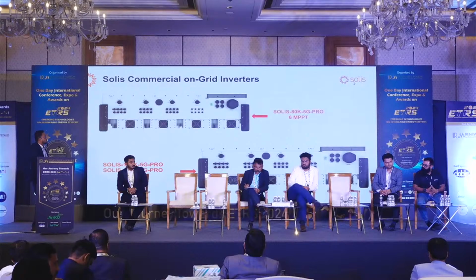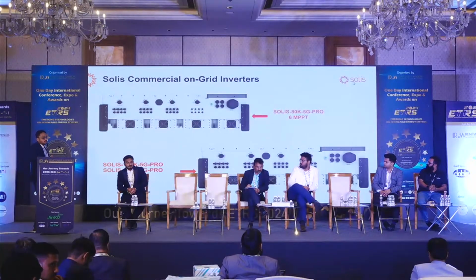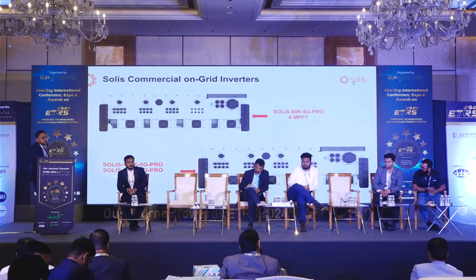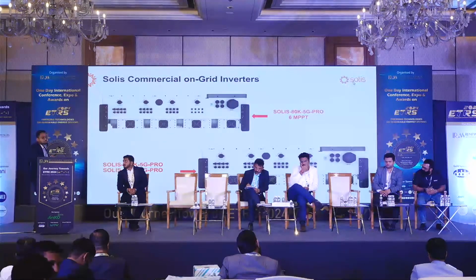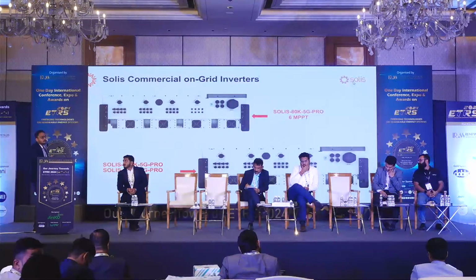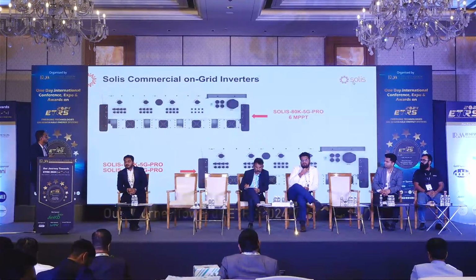This is the design of this model inverter. This is the bottom view of the 80 kilowatt and the 100 and 110 kilowatt. Again, we're providing four separate DC switches for each module. If any customer faces a failure in any module, switch off that DC switch, and the remaining 75% of inverter power will be in generation mode.